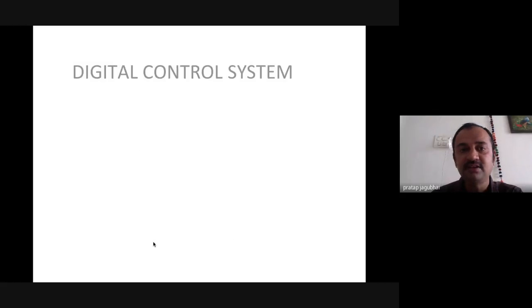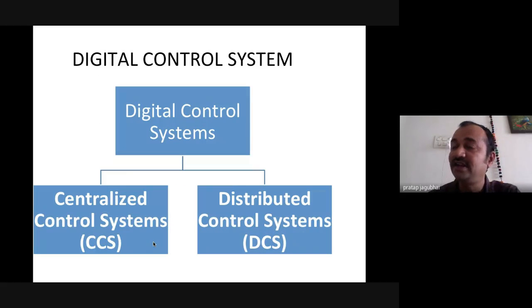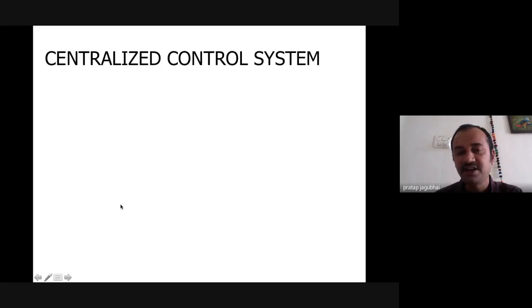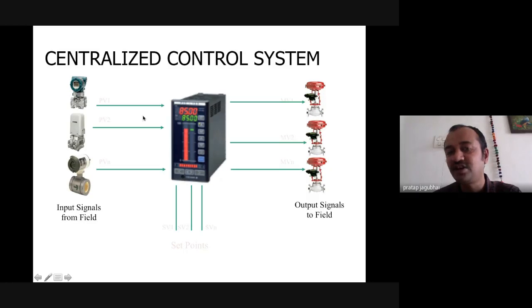Now, on top of that, we can have more advanced control like DCS control, which is a more advanced form of controlling strategy, where you can have your local control as well as centralized control available. This distributed control is very widely used, a combination of local and centralized control. How is it advantageous? Your centralized control can be a PLC or a microprocessor, which will be controlling the parameter and modulating your output to control your output signal.